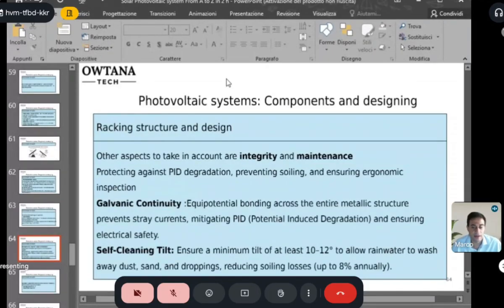Other aspects to take into account are integrity and maintenance, protecting against PID degradation, preventing soiling, and ensuring ergonomic inspection. After that, we have galvanic continuity and self-cleaning tilt. These are higher forms of maintenance. So we should ensure a minimal tilt of at least 10 to 12 degrees to allow rainwater to wash away dust, sand, and droppings, reducing soiling losses up to 8% annually. Of course, you can imagine if our solar module is full of dust, full of sand, its efficiency drops dramatically.